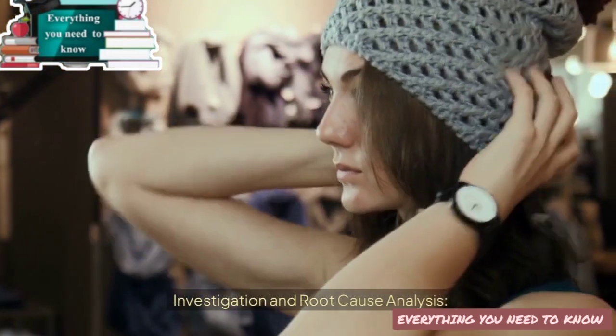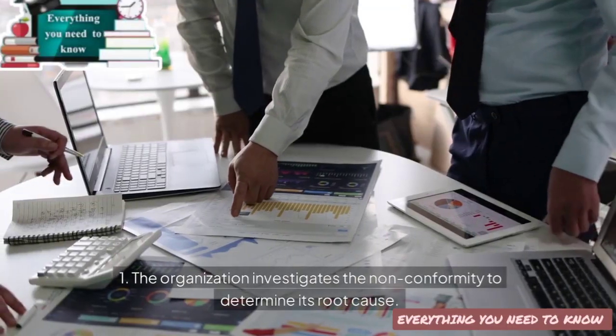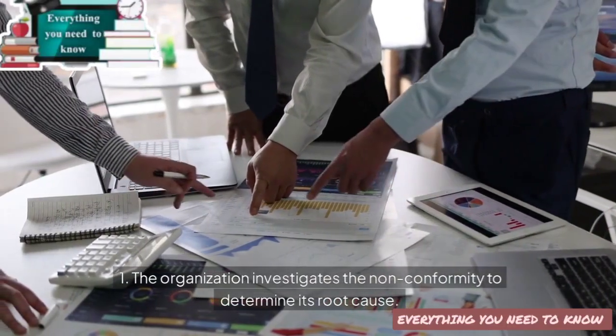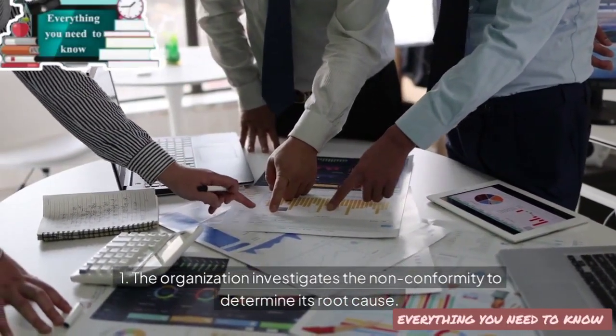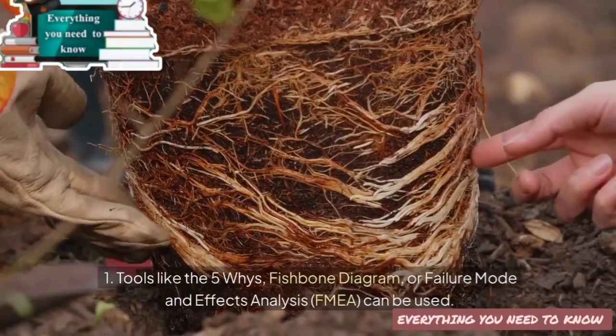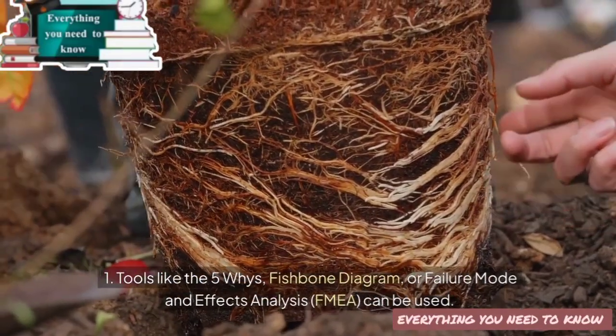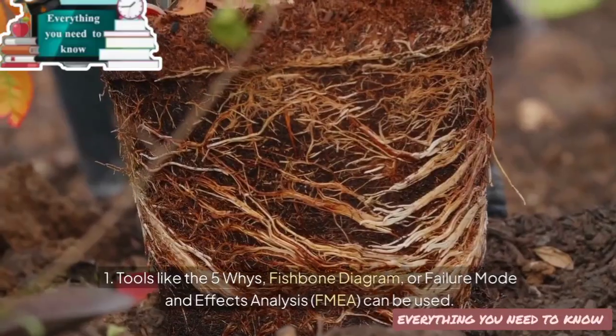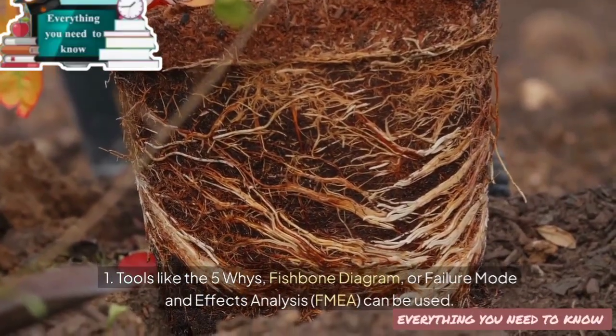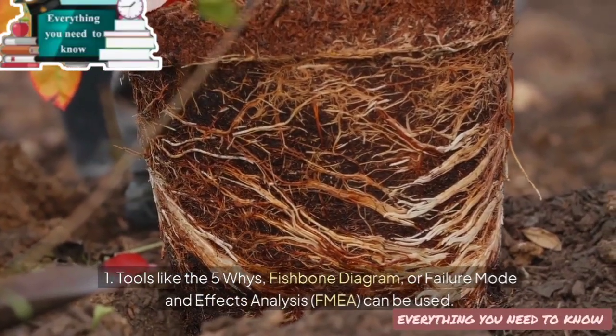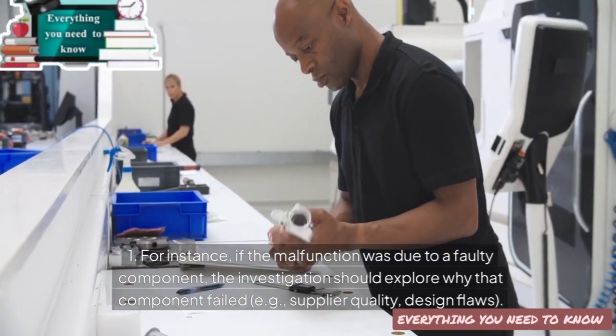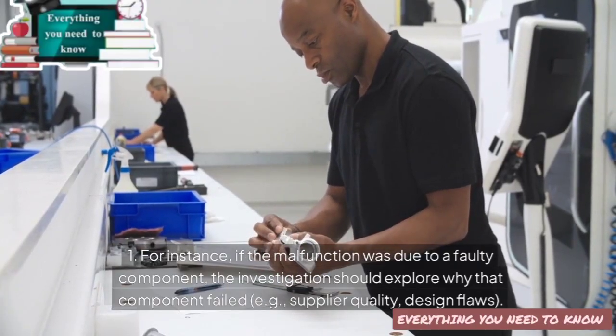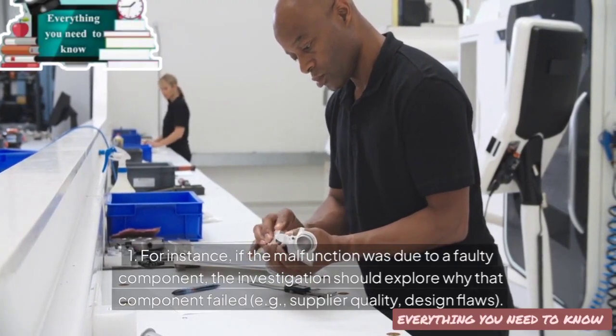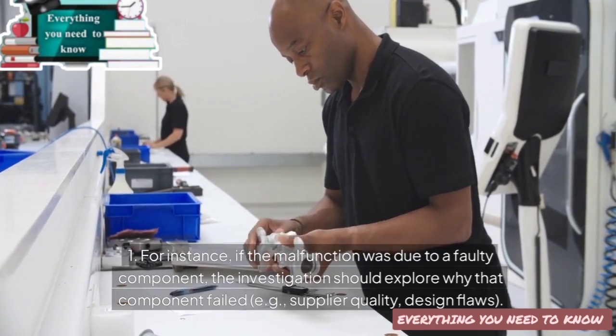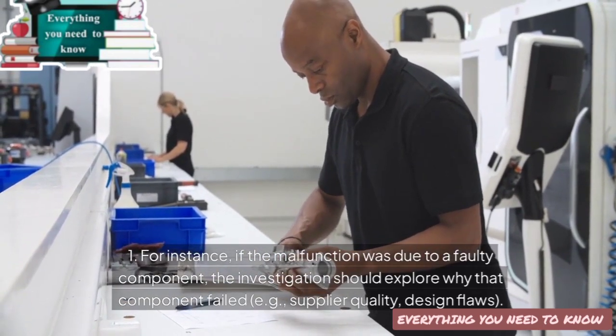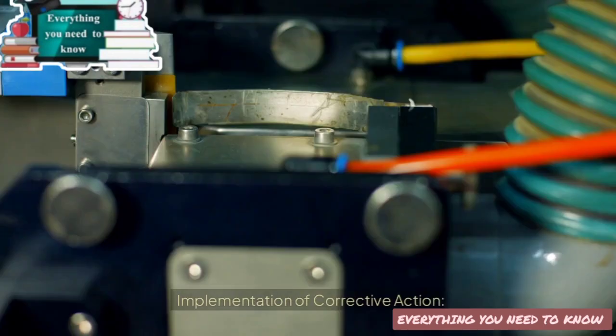Investigation and root cause analysis. The organization investigates the nonconformity to determine its root cause. Tools like the 5 Whys, fishbone diagram, or failure mode and effects analysis, FMEA, can be used. For instance, if the malfunction was due to a faulty component, the investigation should explore why that component failed, for example, supplier quality or design flaws.